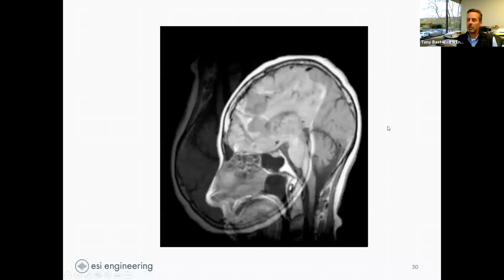So we don't want to get this wrong. We want to make sure vibration levels are low enough for this equipment. We're going to trust that the MRI manufacturers know what they're doing when they put the criteria out there.